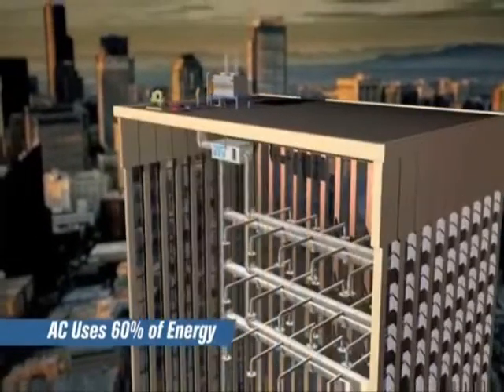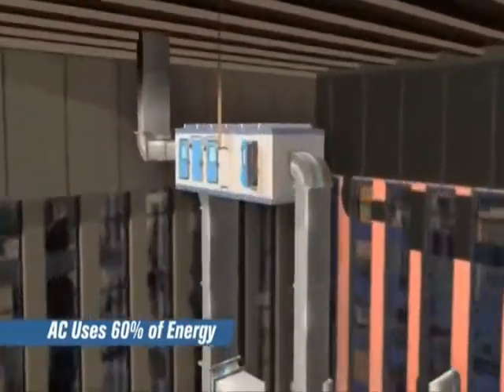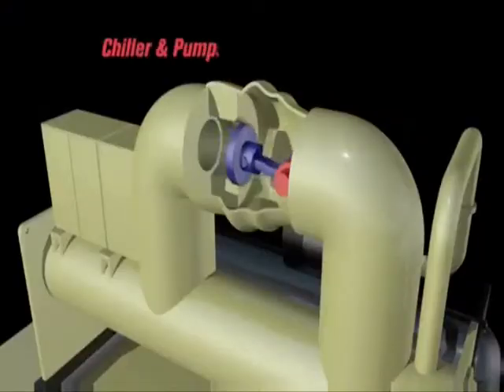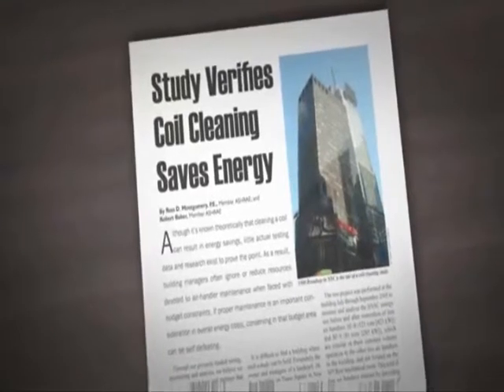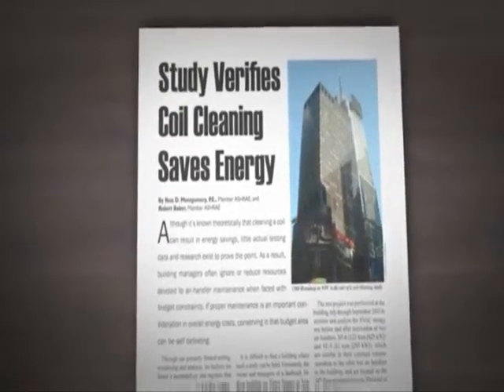In a typical office building, the AC system uses 60 percent of the building's energy, and of this, the chiller and pumps consume 70 percent. The 2006 ASHRAE published study estimated savings of 15 to 30 percent from clean coils.